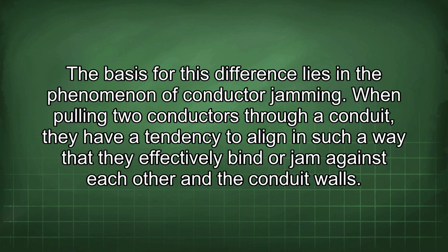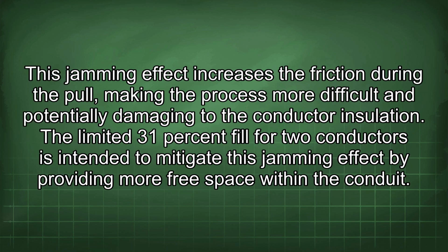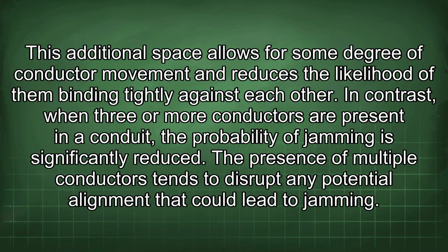When pulling 2 conductors through a conduit, they have a tendency to align in such a way that they effectively bind or jam against each other and the conduit walls. This jamming effect increases the friction during the pull, making the process more difficult and potentially damaging to the conductor insulation. The limited 31% fill for 2 conductors is intended to mitigate this jamming effect by providing more free space within the conduit.